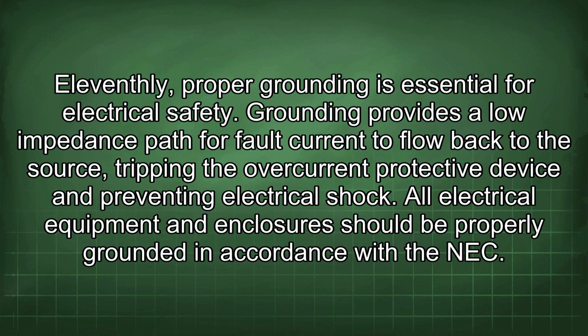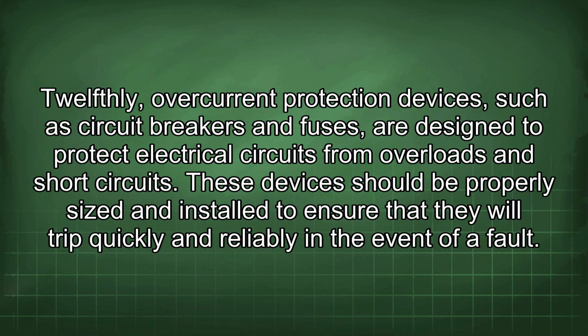Grounding provides a low impedance path for fault current to flow back to the source, tripping the overcurrent protective device and preventing electrical shock. All electrical equipment and enclosures should be properly grounded in accordance with the NEC. Twelfthly, overcurrent protection devices, such as circuit breakers and fuses, are designed to protect electrical circuits from overloads and short circuits.